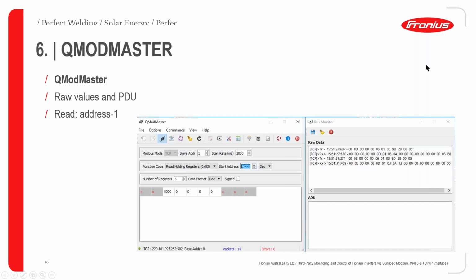The second one, I've shared some slides of this tool previously, is the log files from bus monitor. It's also a good tool. Key information: a lot of controllers and tools do have a -1 embedded offset in the addresses. So the actual addresses you get, you need to offset by -1, which comes to the actual starting address.